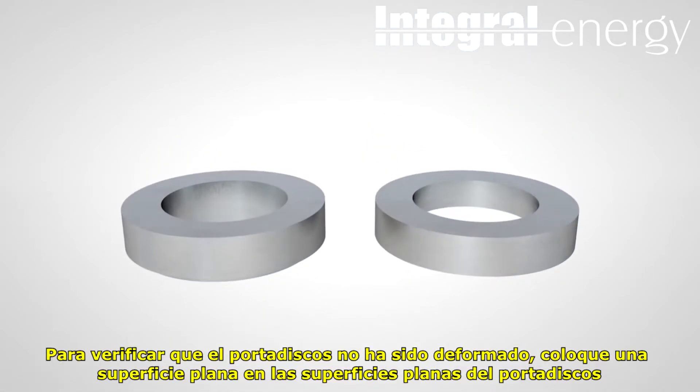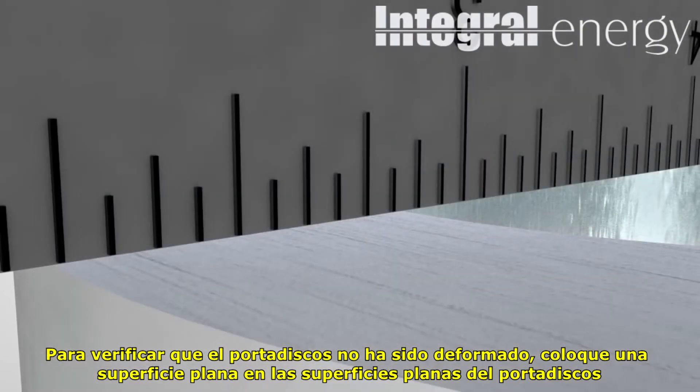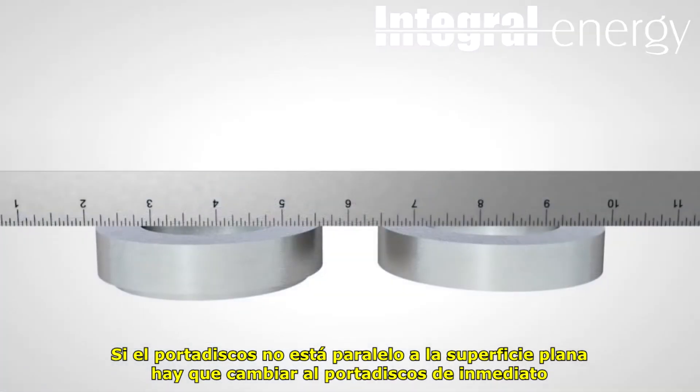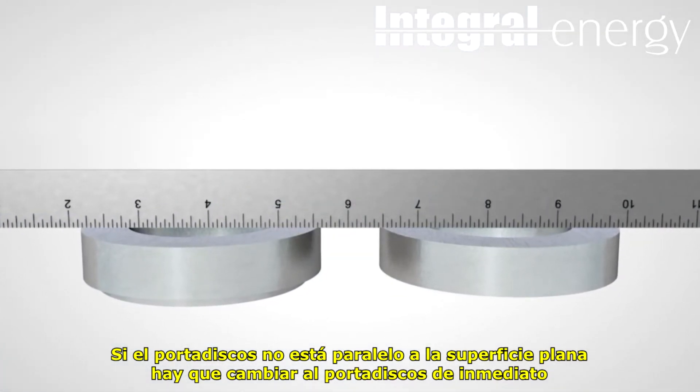To verify that the holder has not become deformed, place a straight edge on the flat surfaces of the holder and hold down. If the flat surfaces are not parallel with the straight edge, the holder should be replaced immediately.